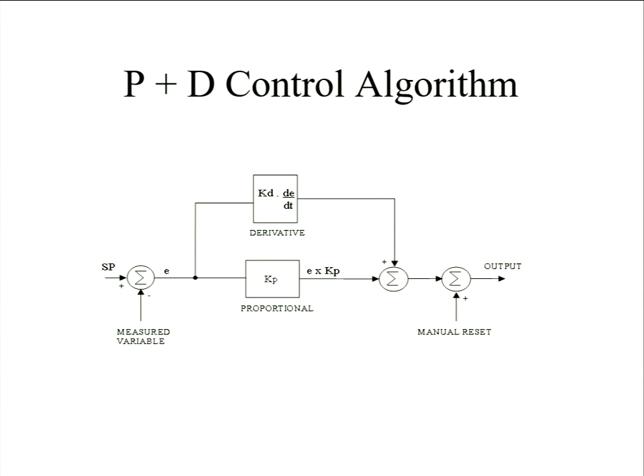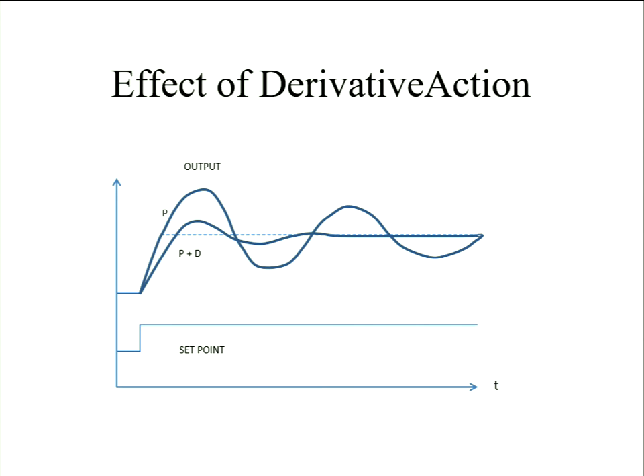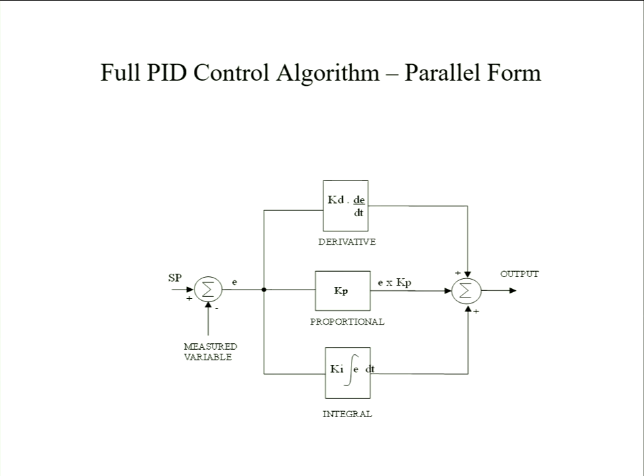So when you're tuning them, you've got to think, what's your real goal? Is it to get within a certain percentage, or settle within a certain time? Can you accept overshoot, or do you need it to approach effectively from one side? Obviously you want a stable process and you don't want sustained oscillations, but you've also got to look at what you're asking your controlling device to do. Say, I've got very good control but my valve's doing that. Well, trial and error.